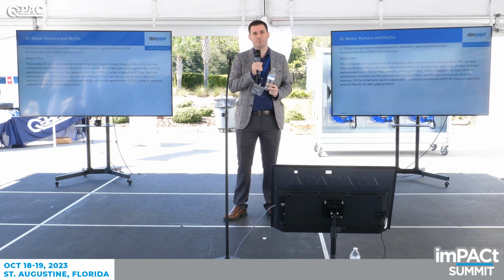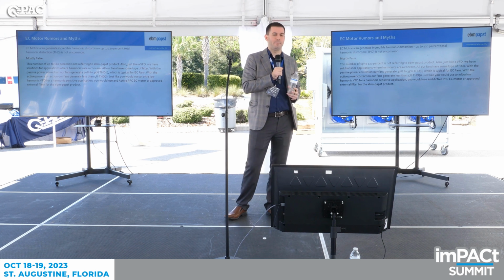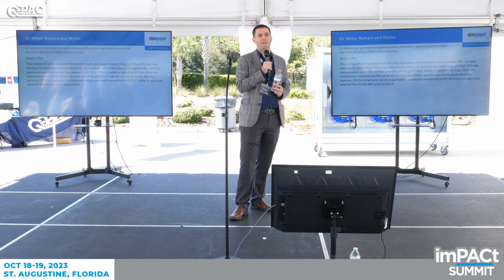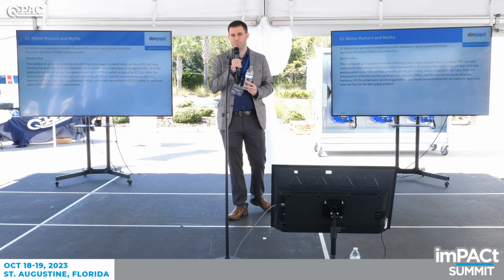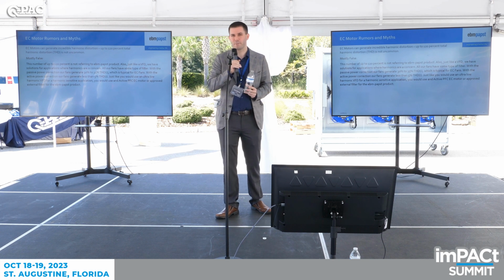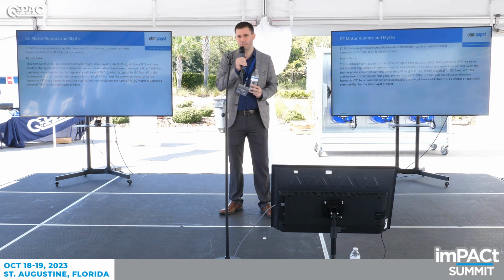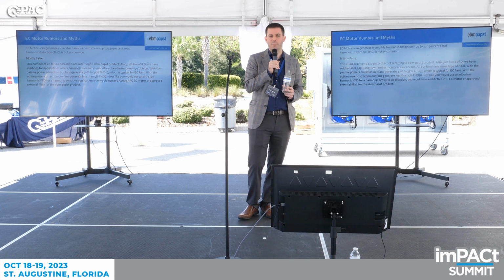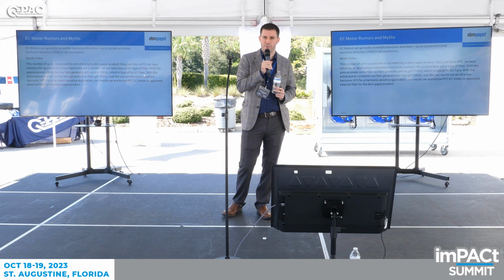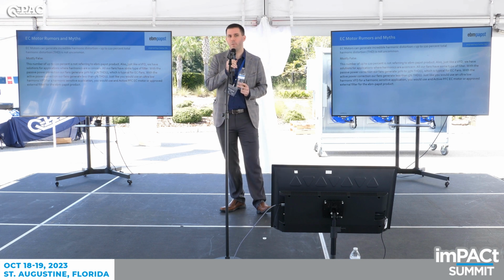This is going to be fine for most buildings. Hospitals, lots of times, require low harmonics. Sometimes there might be states that require low harmonics in their government buildings. For that, we have external filters that you can use. We have some really good partners that have designed some filters for us. That'll get you to about a little less than 5% harmonic distortion at full load. And then we also have active filters built into the back of them on some of our product. So if you use that, you'd get to about under 2% harmonic distortion at full load, and it'll actually hold that pretty much down to 30% load.